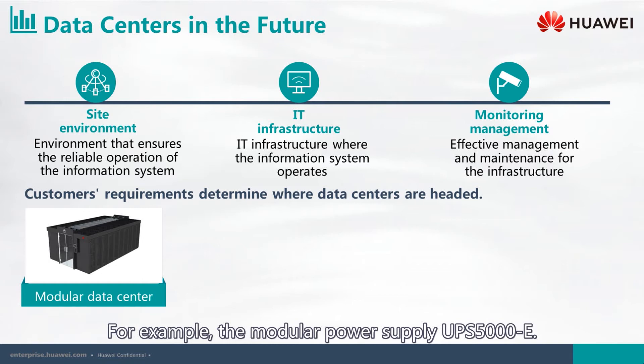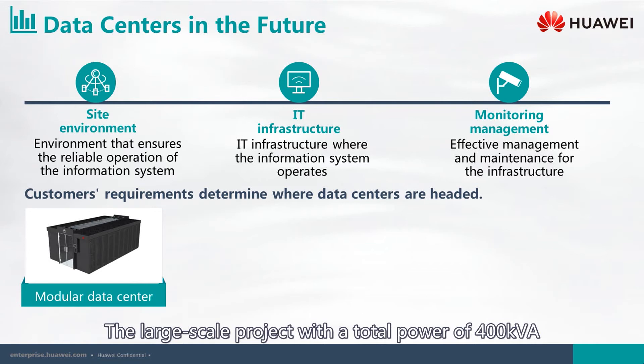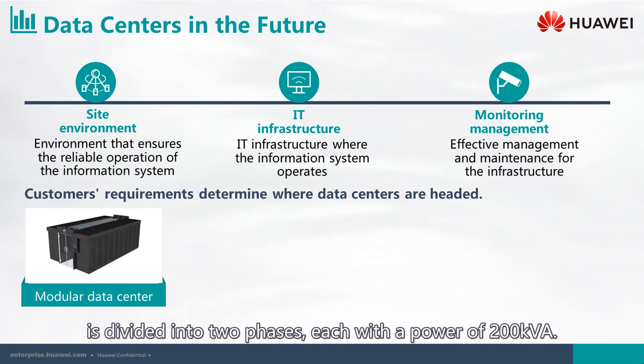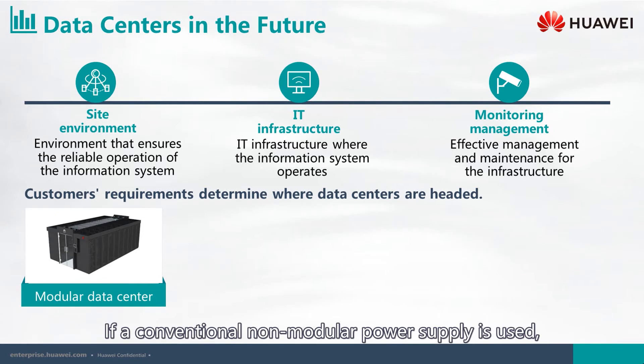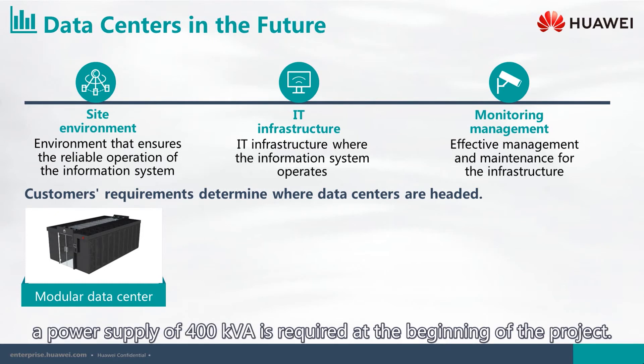For example, the modular power supply UPS 5000E — a large-scale project with a total power of 400 kilovolt-amperes — is divided into two phases, each with a power of 200 kilovolt-amperes. If a conventional non-modular power supply is used, a power supply of 400 kilovolt-amperes is required at the beginning of the project.